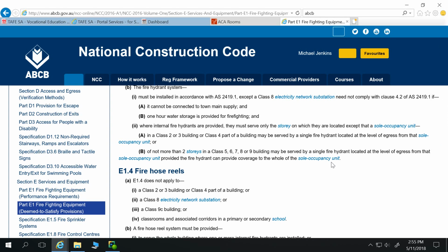The difficulty, so this is saying, this is telling us we could possibly have a fire hydrant on the top floor and then one on the bottom floor, if the hydrant from the top floor can serve the middle floor, or the hydrant from the bottom floor can serve the floor above. That's what that is telling us.